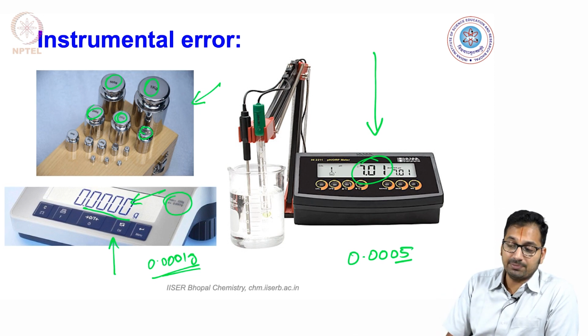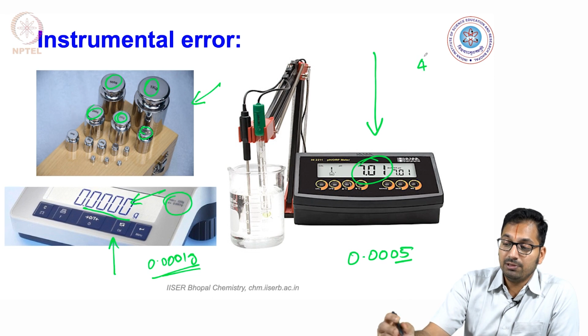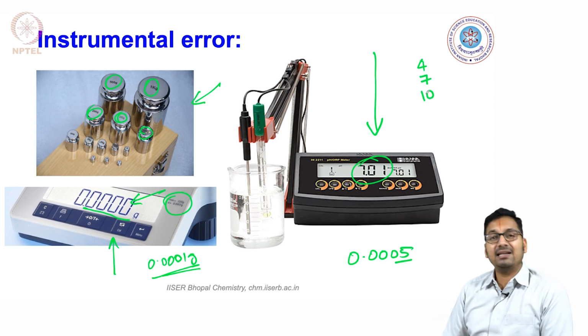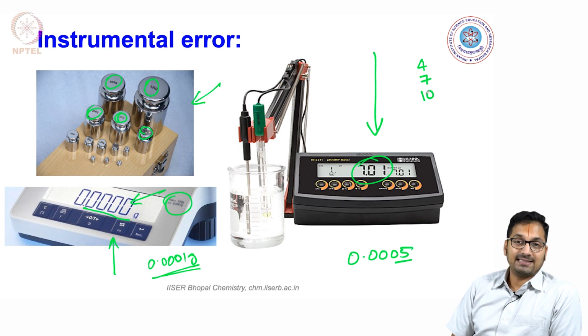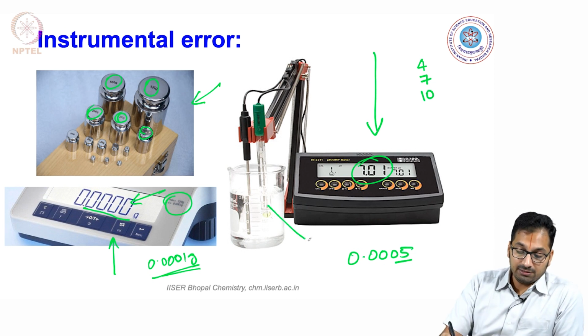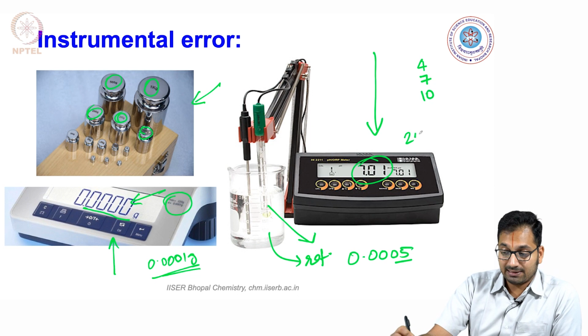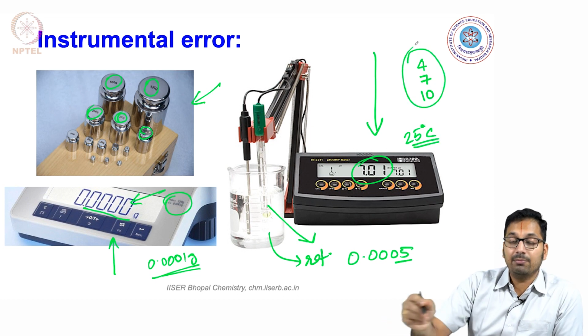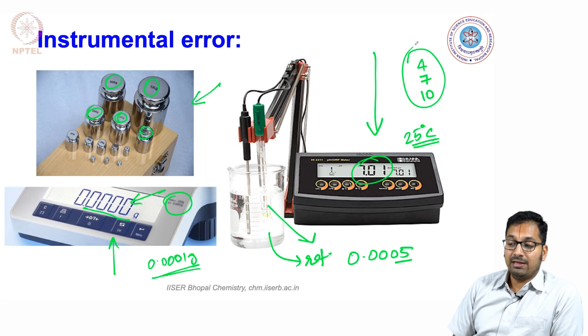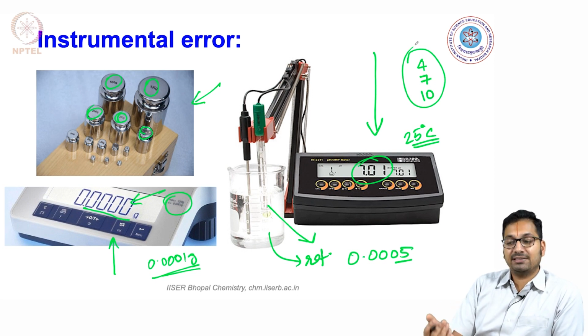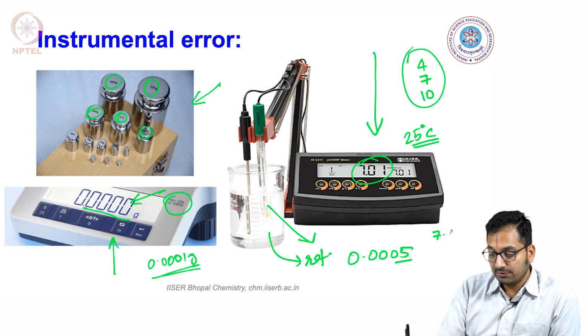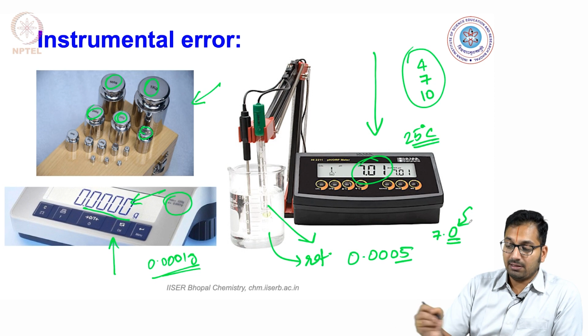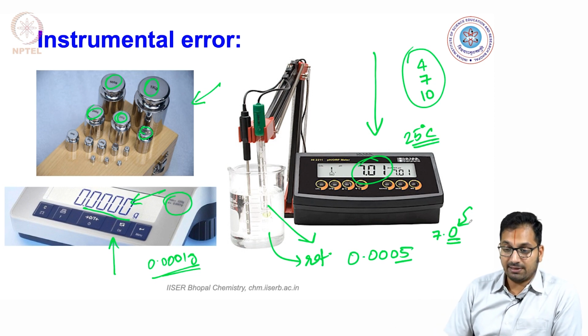And how would you calibrate a pH meter? Quite commonly people use standard pH solutions, at least 3 different pHs, that is pH 4, 7 and 10, and you would be using the probe in the reference solution and using the same pH meter at, let's say, a given temperature, and then calibrate the pH. So this would ensure that as a function of pH, even if you are changing the temperature, you are carefully calibrating things in order to ensure that whatever you are measuring is the right pH. In general, for pH, people generally give only 1 decimal, indicating that the precision exists within that decimal only.